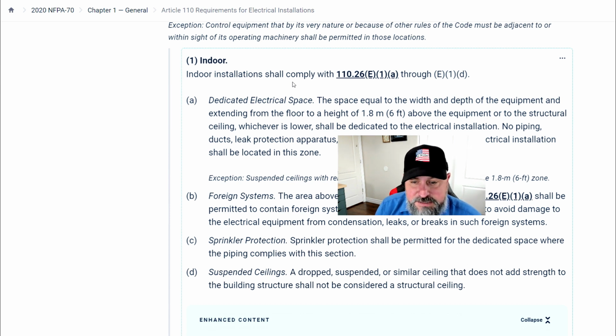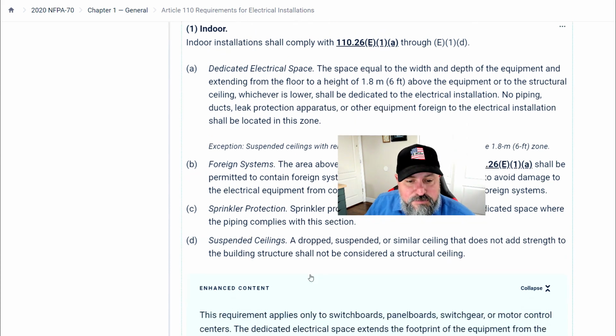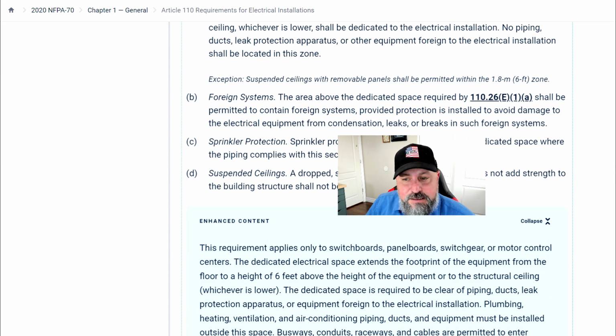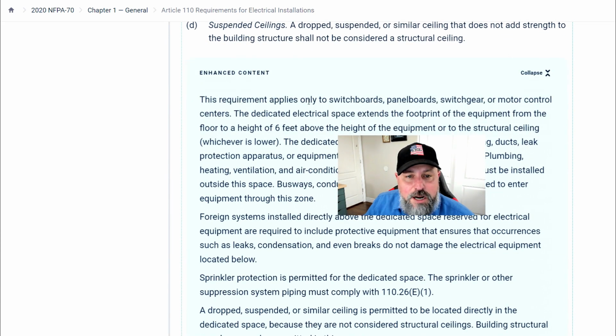Foreign systems: the area above the dedicated space required by 110.26(E)(1)(a) shall be permitted to contain foreign systems, provided protection is installed to avoid damage to the electrical equipment from condensation, leaks, breaks, and such. So that's if it is preventing the leaks from the foreign system. Sprinkler protection shall be permitted for the dedicated space where the piping complies with this section. Suspended ceiling: a drop, suspended, or similar ceiling that does not add strength to the building structure shall not be considered a structural ceiling. This requirement applies only to switchboards, panelboards, switchgear, or motor control centers.